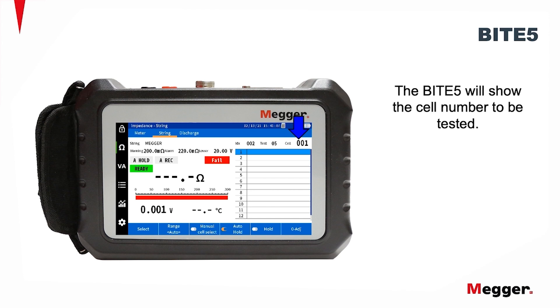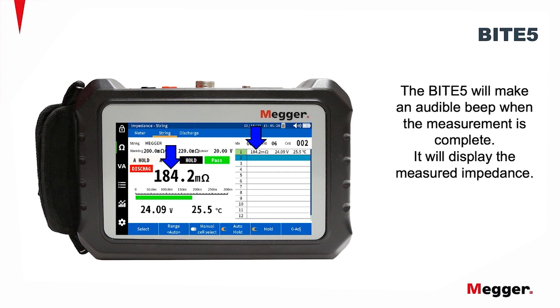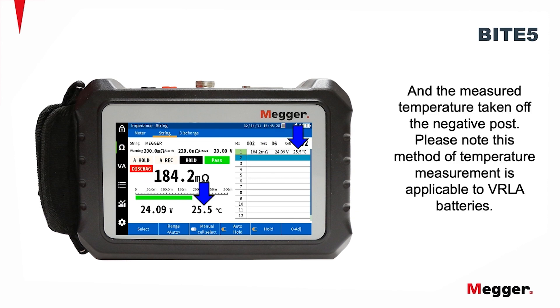The BITE5 will also show the cell number to be tested. Now, measure the impedance of the first cell. The BITE5 will make an audible beep when the measurement is complete. It will display the measured impedance, the measured voltage, and the measured temperature taken off the negative post.